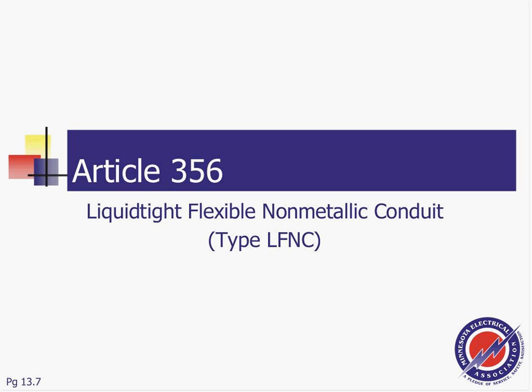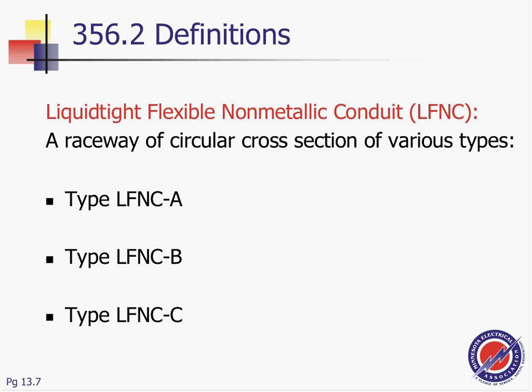Now, one more conduit for you, if that's not enough. It's called Liquidtight flexible non, and I emphasize the word non. This is your plastic nonmetallic conduit. Nothing is metallic in it. And as the name implies, anything nonmetallic is perfect insulation for highly corrosive environments. That's it, highly corrosive environments. That's the application, really. So moving to this conduit, let's go ahead, guys. This is 356. Let's go to 356 and look at a few things about it.